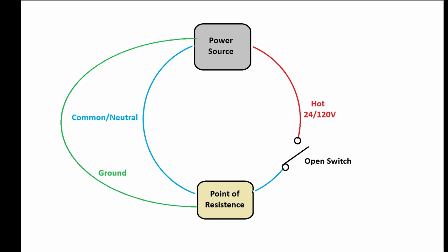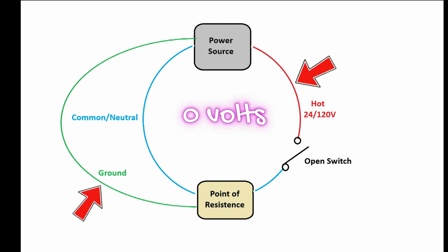Now here's the problem with that. If I were to put my probe on, let's say, the hot wire and my other probe on ground and I'm reading 0 volts, once again, that does not tell me whether or not I have a power source problem, or maybe I have a problem with a circuit not being properly grounded. So that voltage reading doesn't really mean anything to me. Now, if I expect to see 120 and I do read 120 off of ground, then that's telling me I have a properly grounded circuit.